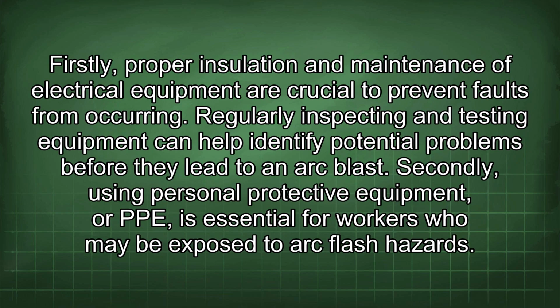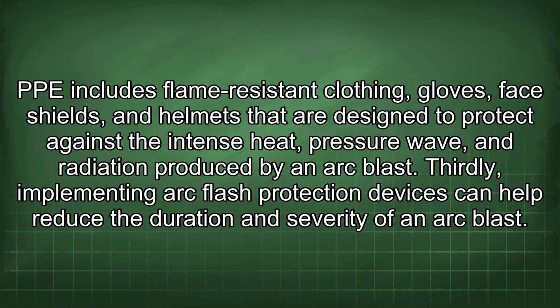To mitigate the risks associated with arc blasts, it's essential to implement appropriate safety measures. Firstly, proper installation and maintenance of electrical equipment are crucial to prevent faults from occurring. Regularly inspecting and testing equipment can help identify potential problems before they lead to an arc blast. Secondly, using personal protective equipment, or PPE, is essential for workers who may be exposed to arc flash hazards. PPE includes flame-resistant clothing, gloves, face shields, and helmets that are designed to protect against the intense heat, pressure wave, and radiation produced by an arc blast.